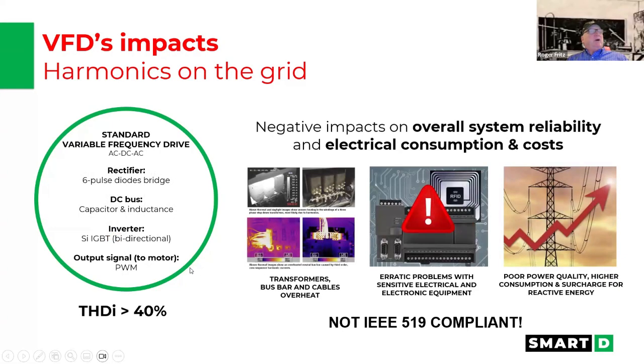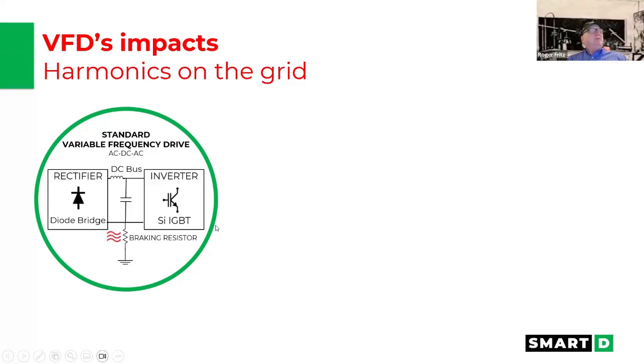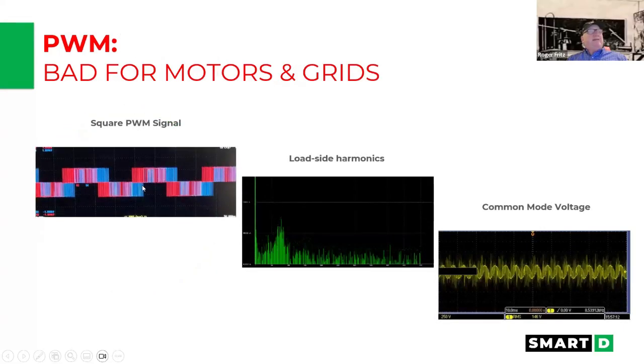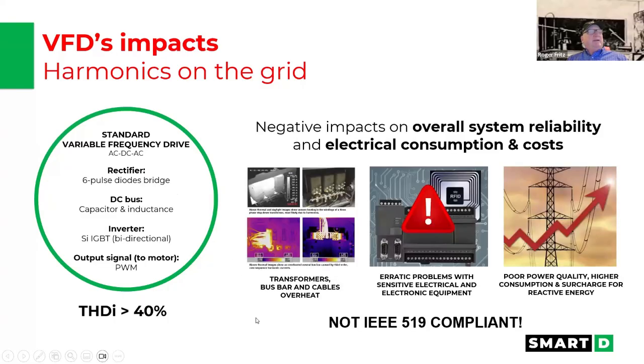And so what they've been doing for quite a while also is they've been taking the variable frequency drive, which as the standard is a 6 pulse diode. And then you've got your bidirectional IGBTs, and then that gives you your PWM output. The issue is that these harmonics that are shown on the previous slide, both on the load side and the input side, what happens is, with not being IEEE compliant, you'll get transformers and cable overheating, and then you'll also get all kinds of erratic problems that people aren't aware of that are happening in their PLCs, their process controllers, in plants. And so it ends up just creating more and more of an issue.